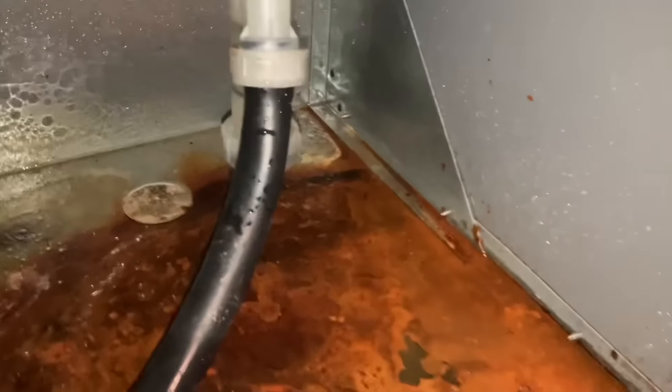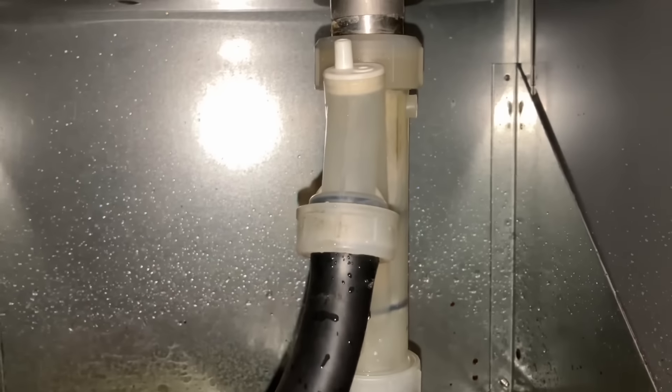I'll clean that off in the sink. So in my truck, I replaced the neutralizer media — I buy it in bulk. It's about a 30 or 40 pound box of those minerals with the little fairy dust. See those little specks of white? Then I used some Spray Nine and cleaned all that greasy black residue that was on there. I cleaned it the best I could and also cleaned off the ball. I don't know what's up with that blue residue, but it's definitely not coming from the shop rag.